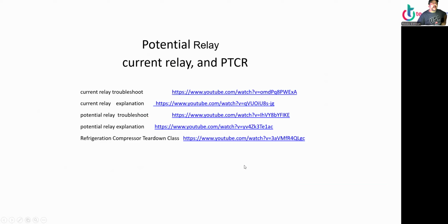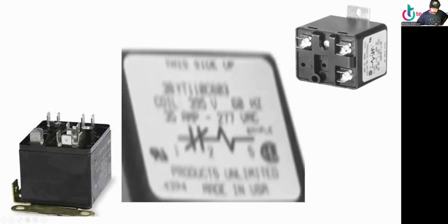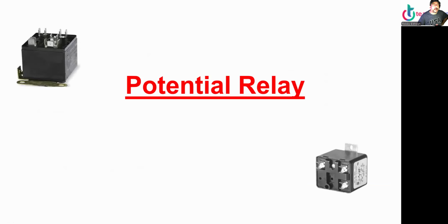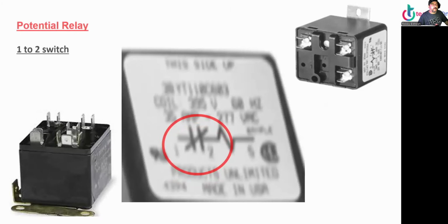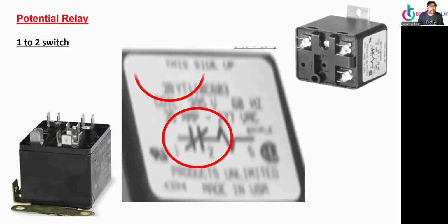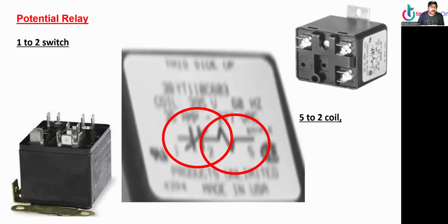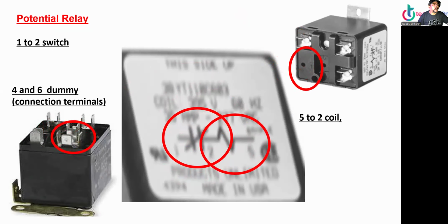Alrighty. Now let's move on to the potential relay, current relay, and PTCR. A lot of videos out there. All right, potential relay. I call them electrical starters, because if you tell the customer, I replaced a relay, that's $150, they're going to go crazy. $150 for a relay? Well, it's not just a regular relay, it's a potential relay, okay? All right, let's move on. Potential relay: 1 and 2 is the switch, 5 to 2 is the coil, and 4 and 6 are dummy, they don't go anywhere.